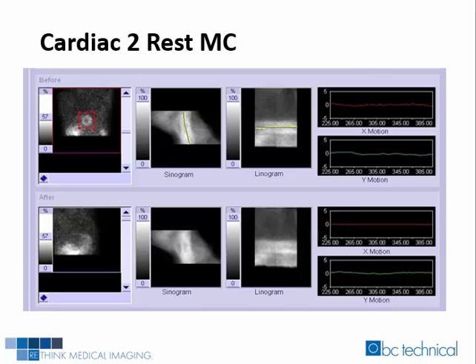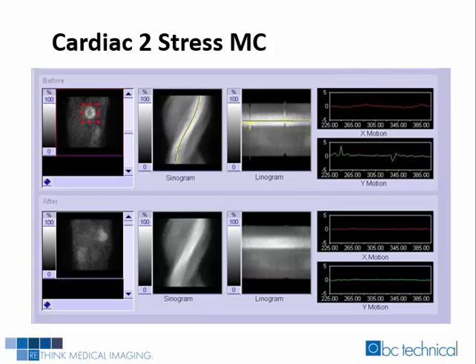Cardiac II's resting study showed less than one pixel of motion before automatic motion correction was applied. The motion-corrected dataset displayed the study with less than one pixel of motion — the same results as the non-motion-corrected. Cardiac II's stress study showed greater than three pixels of motion before automatic motion correction was applied. The motion-corrected dataset displayed a study with almost zero pixels of motion, correcting three pixels of motion.